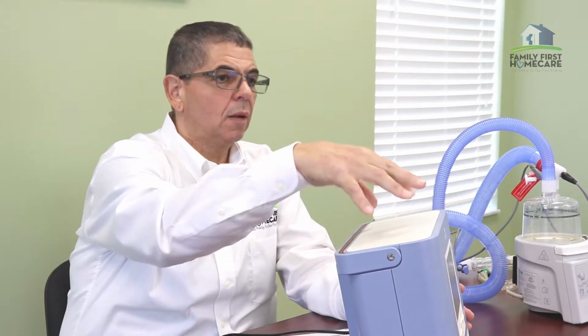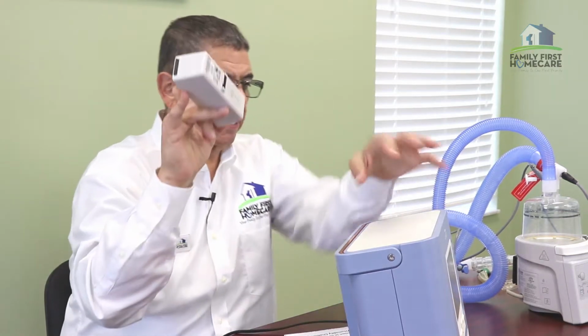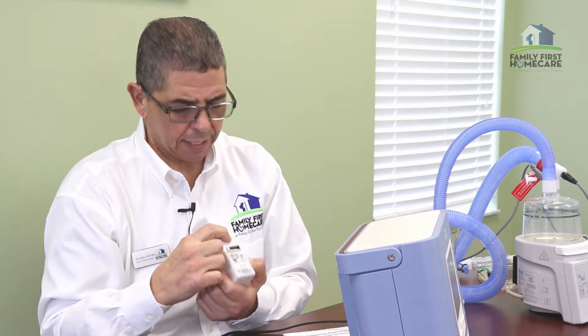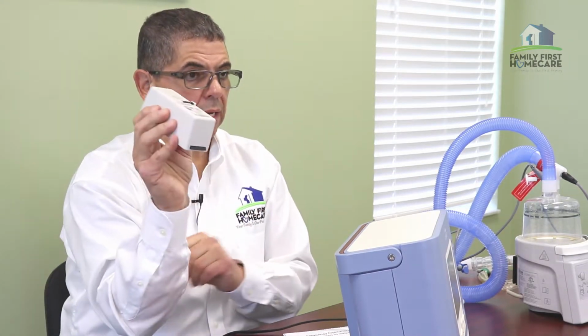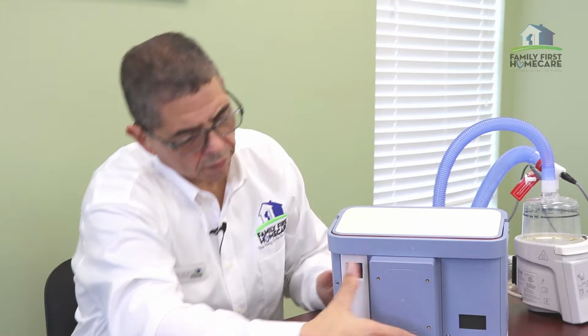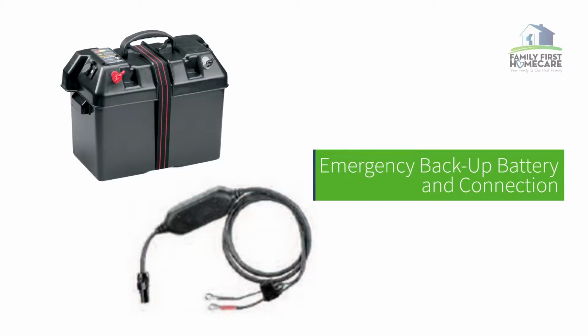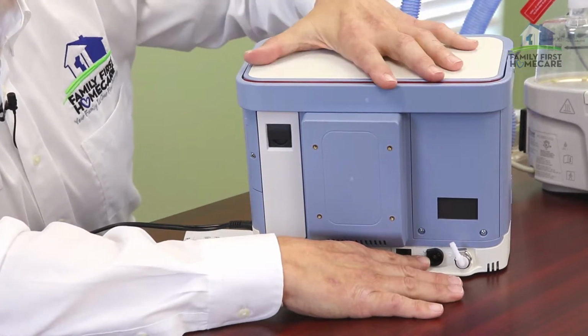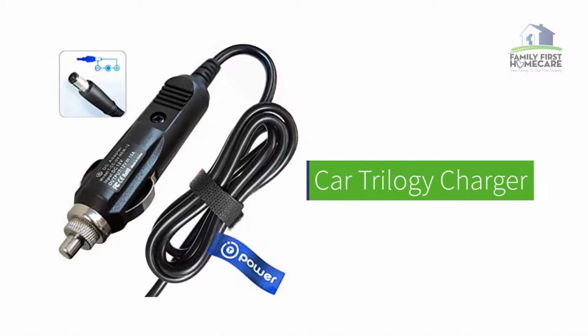Okay, so besides the detachable battery, you have an internal battery inside as well. The internal battery, even if this is not charged, will last about 4 hours by itself without being plugged in. You can actually see that the battery lights up full, and it will clip right in the back. You'll see over here all the other alternate sources of power. A marine battery will attach right in over here. That will give you about 12 hours, so a total of about 24 hours between all the batteries. Also, your car adapter will plug in over here. It's very important that you save the integrity of the machine by protecting the battery.